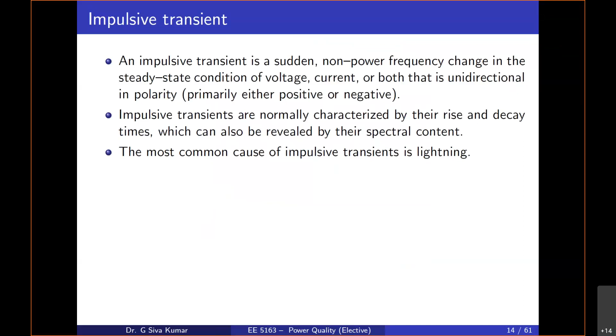We have non-steady state phenomena and steady state phenomena. This impulsive transient, related to non-steady state phenomena, is mostly due to lightning. The definition says an impulsive transient is a sudden non-power frequency change in the steady state condition of voltage or current or both, unidirectional in polarity, primarily either positive or negative.